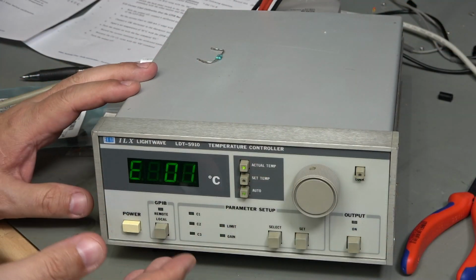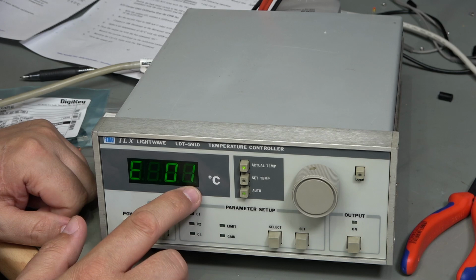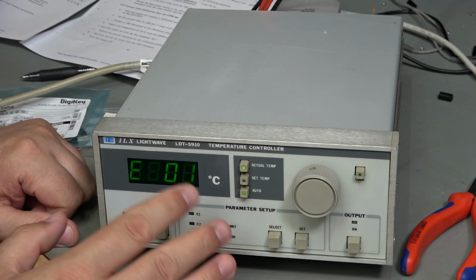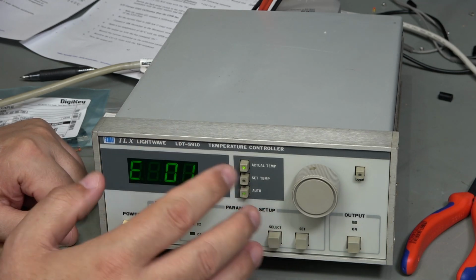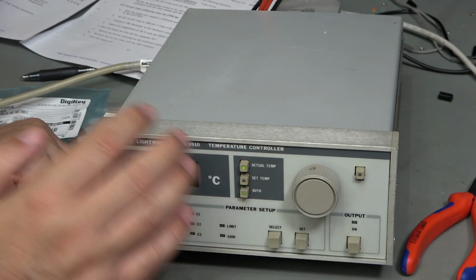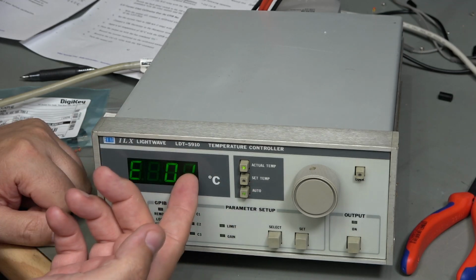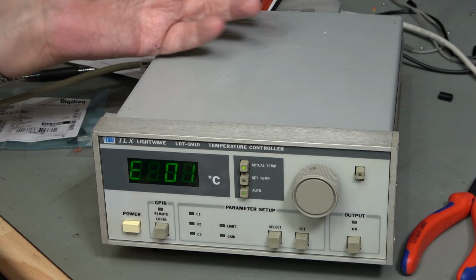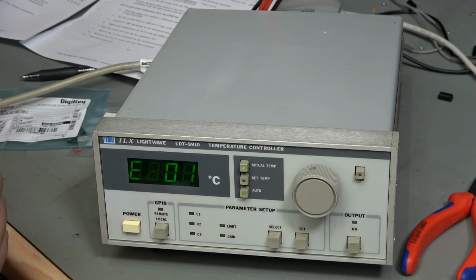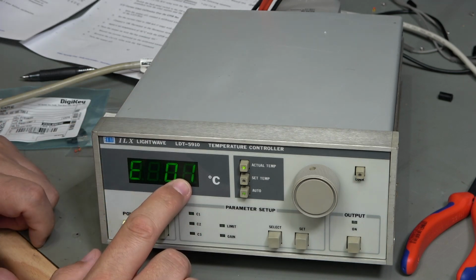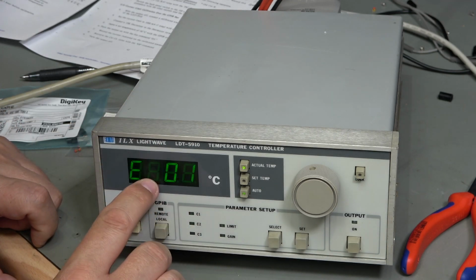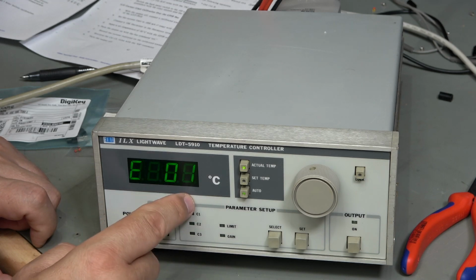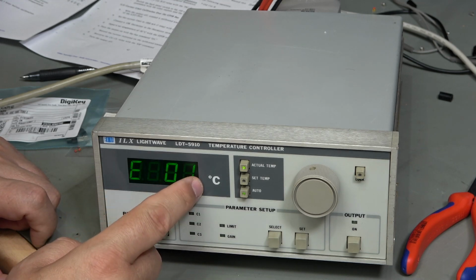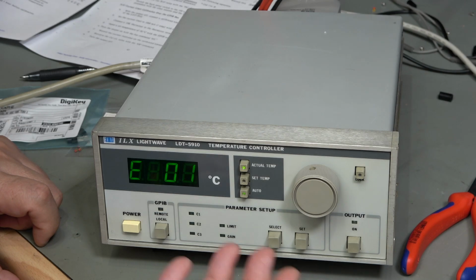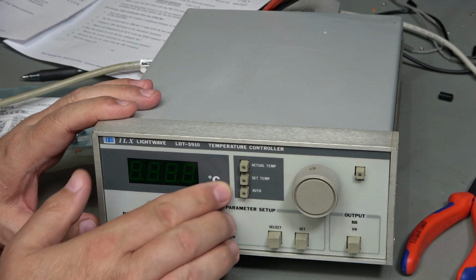Okay, so something quite interesting has just happened. It was working, except it was giving me a wrong reading. So I set out to calibrate it, and I've just been testing the GPIB, and that all seems fine. And it was reading a temperature, just not a very accurate temperature, and I would warm up the thermistor and the temperature would rise. So everything seemed to be working absolutely fine until a minute ago when it just stopped working. So E01, I've just looked that up, and that stands for AD overrange. Now before it was displaying that, it was displaying E02, which is the calculation of temperature failed. So something has definitely gone wrong there.